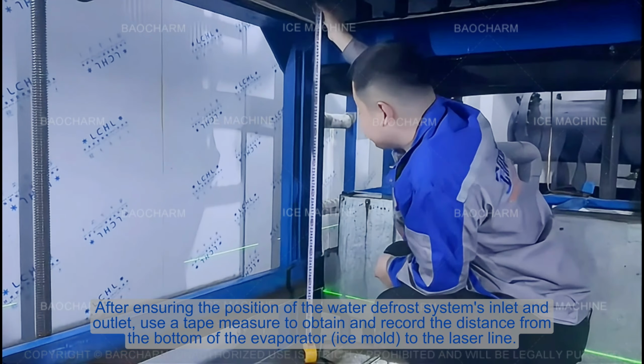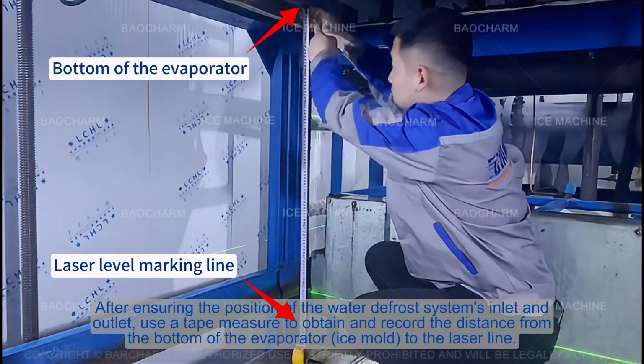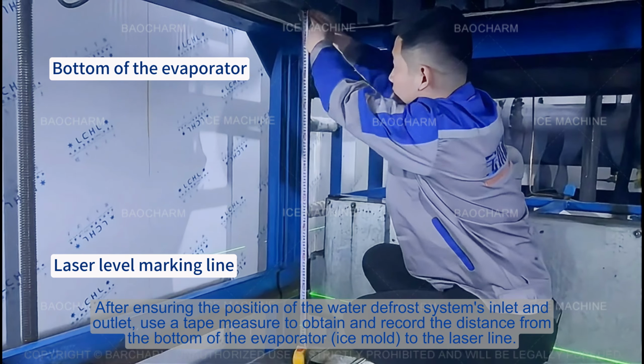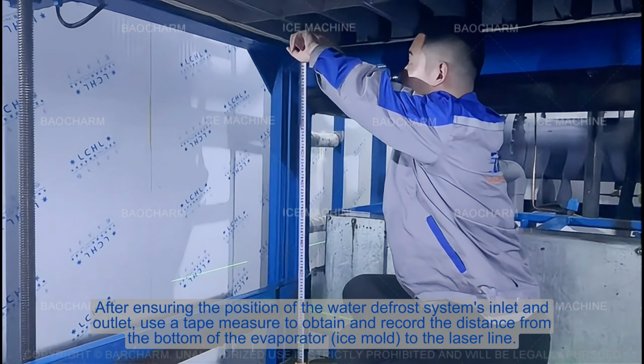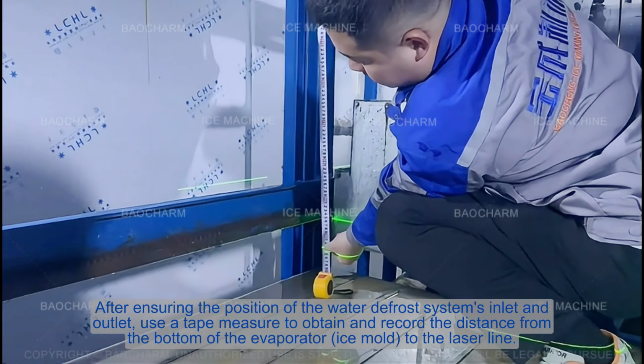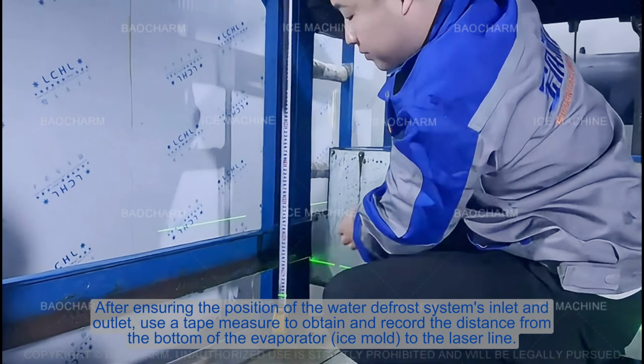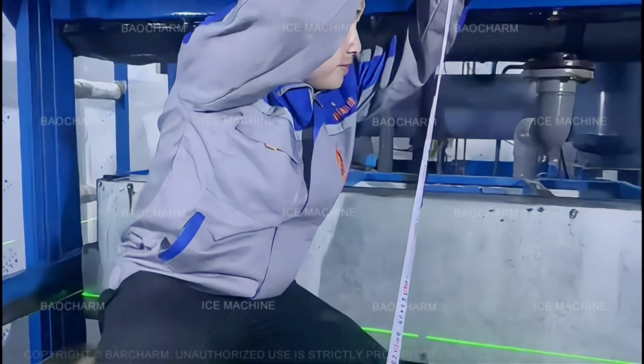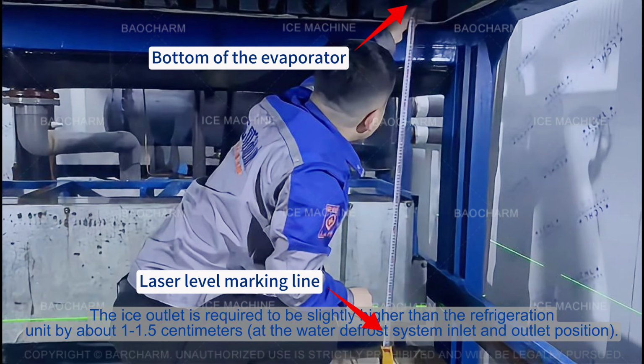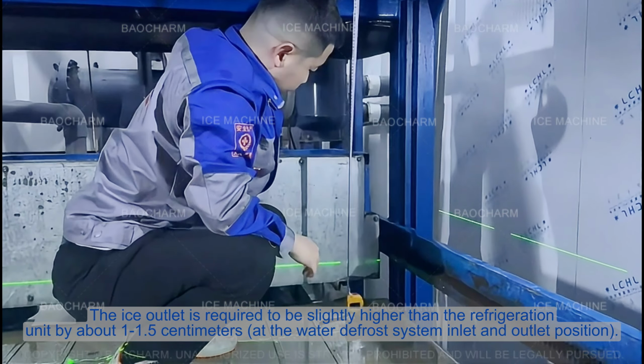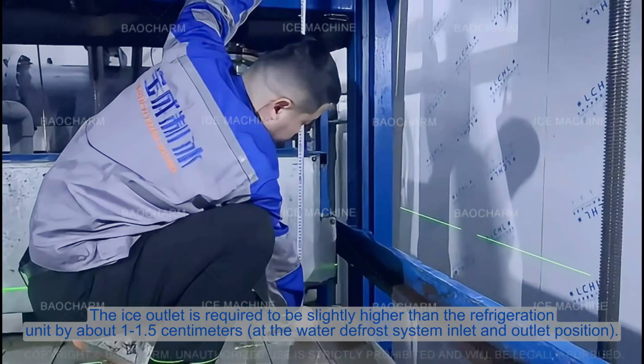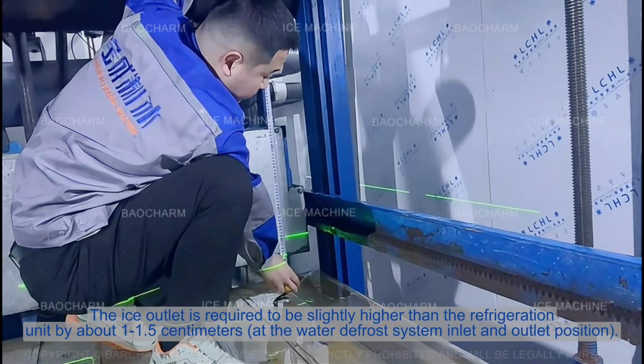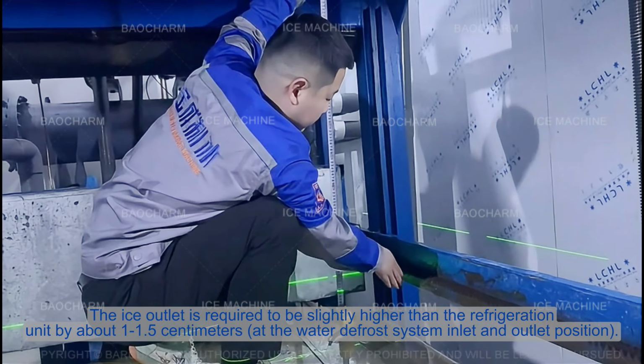After ensuring the position of the water defrost system's inlet and outlet, use a tape measure to obtain and record the distance from the bottom of the evaporator ice mold to the laser line. The ice outlet is required to be slightly higher than the refrigeration unit by about 1-1.5 centimeters at the water defrost inlet and outlet position.